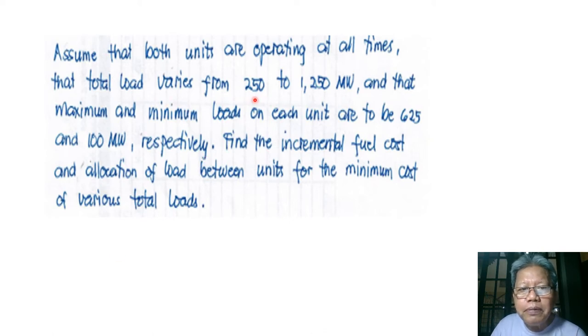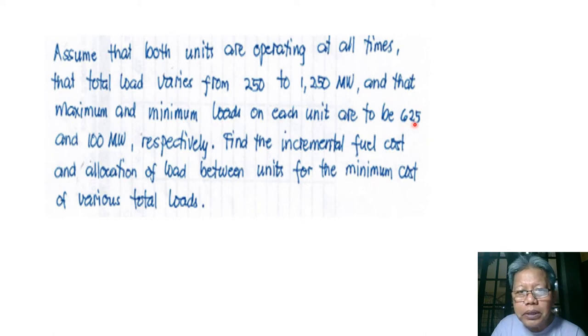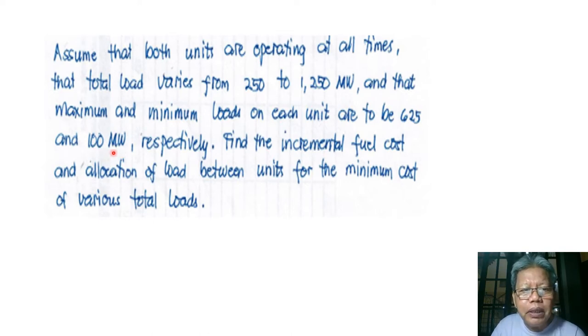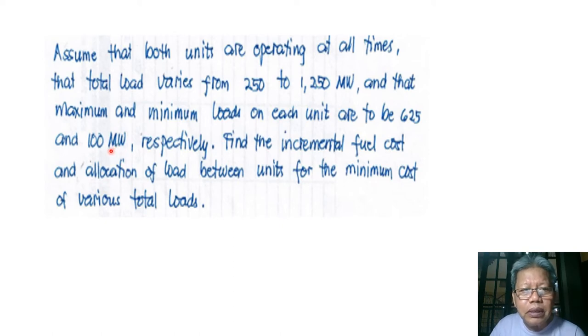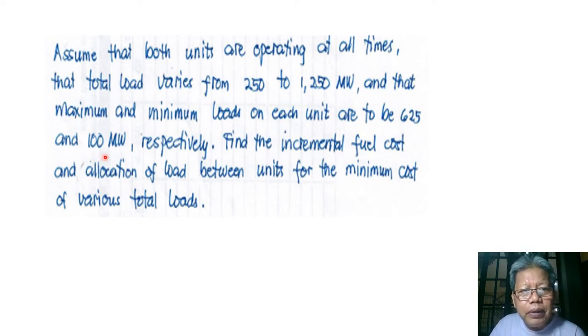Note that load varies from 250 to 1250 megawatts, and each unit can operate only up to a maximum of 625 MW and must operate at a minimum of 100 MW. Units cannot operate at very light loads like 10 or 20 MW because at very light load the vibrations of the generating units become very severe and are only acceptable when the unit is loaded up to at least 100 MW.